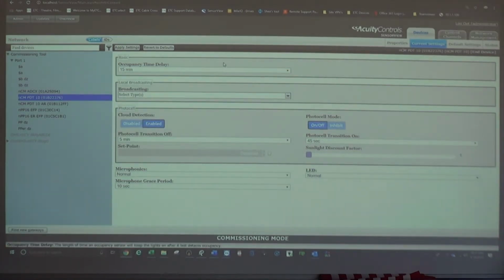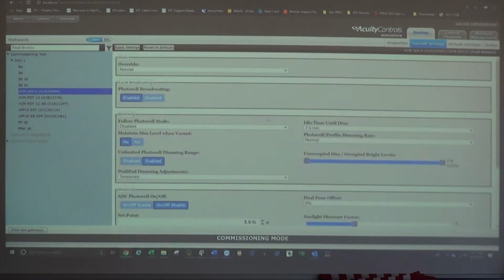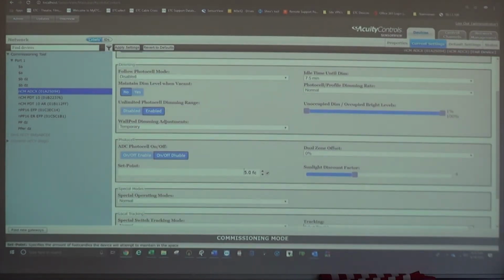And I told you how to override the photocell, but I didn't tell you guys how to set the set point. If you go to your photocell, there's a setting called set foot candles. If it is too dim, increase this number; if it's too bright, decrease the number, because this is what it's reading at the top. This is probably around 80 foot candles over here, but it's only reading 5 at the ceiling.